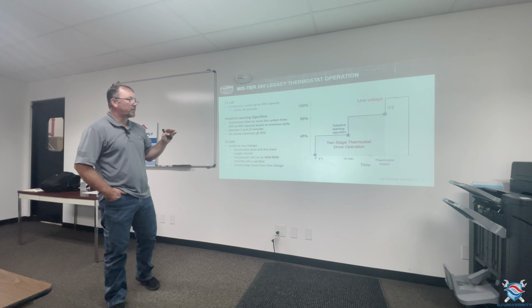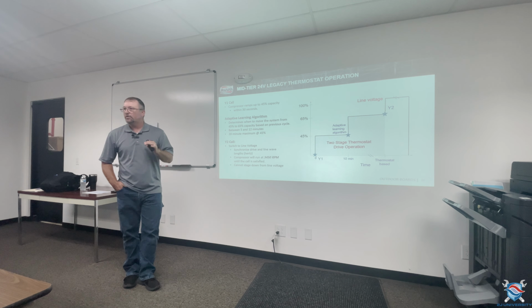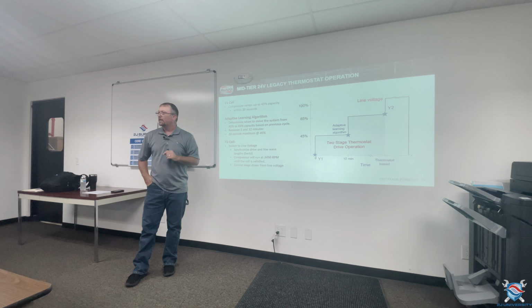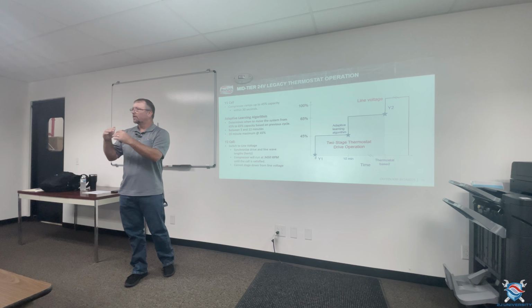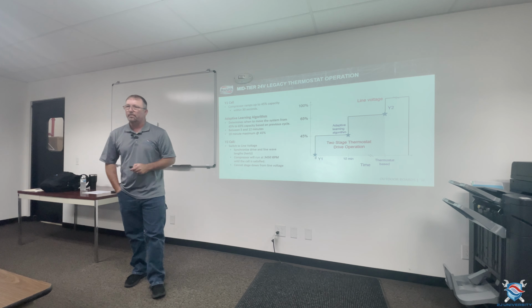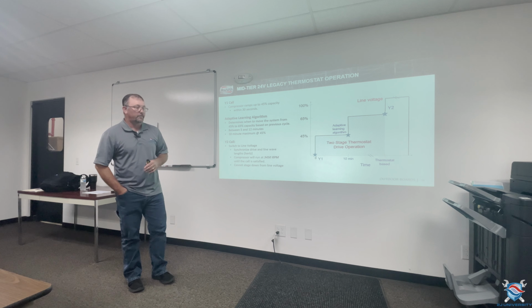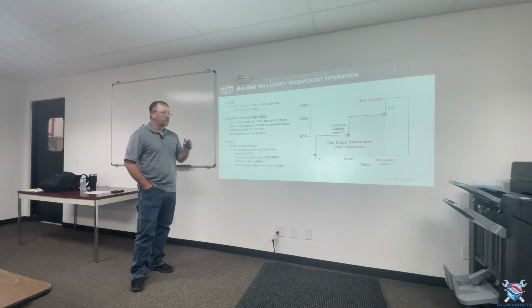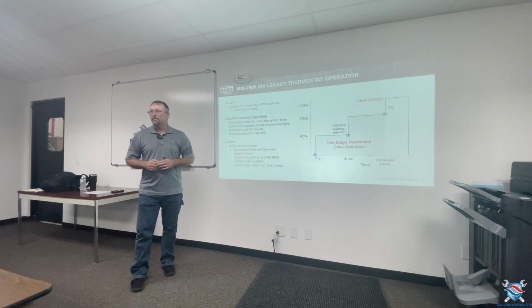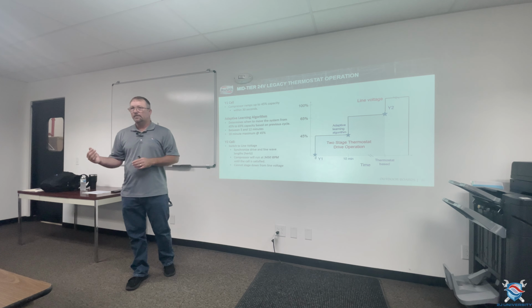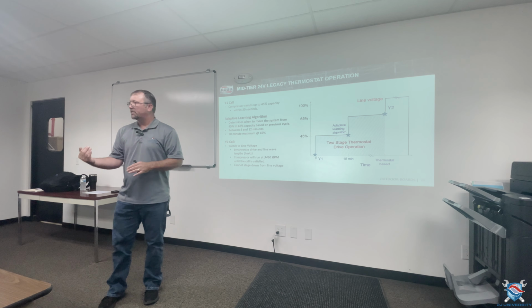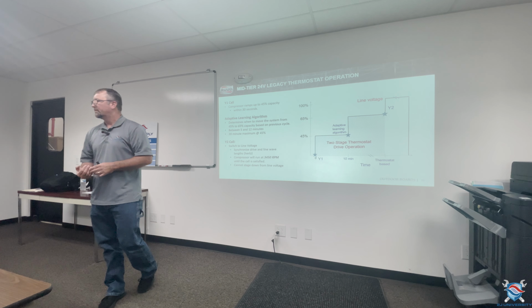Now, this does build an algorithm in there, so your starting point may be different depending on how long your runtime was versus the previous run cycle. So it builds an algorithm as this unit runs in that 24 volt application. So if it ran a really short time on 45% and staged right to second stage, it may jump right into second stage its next start. Okay?